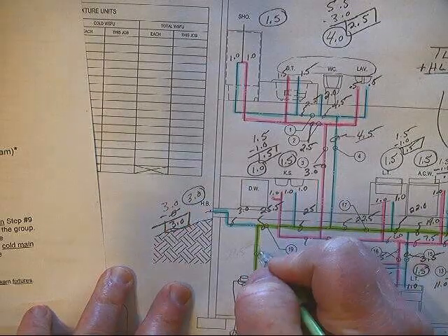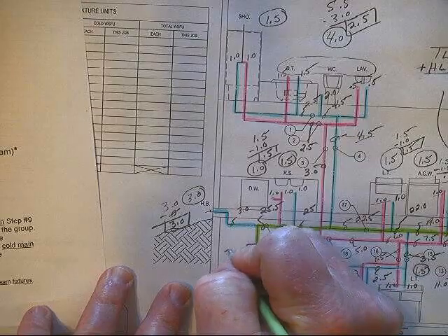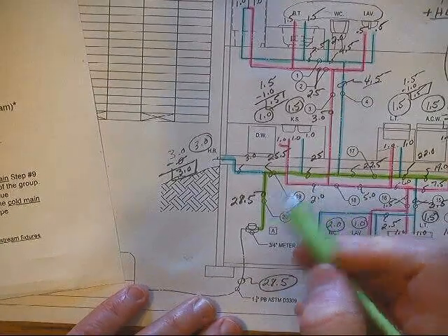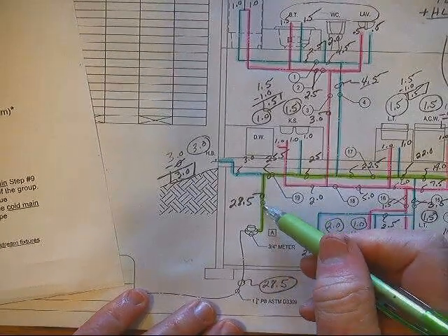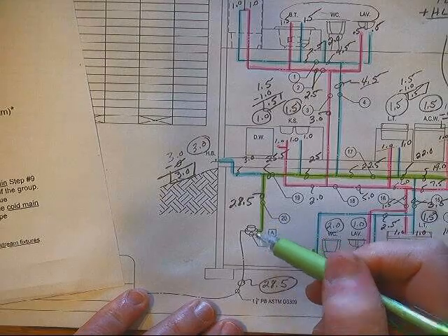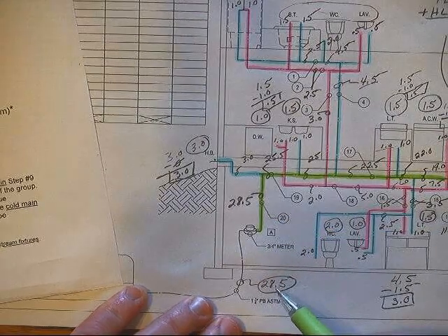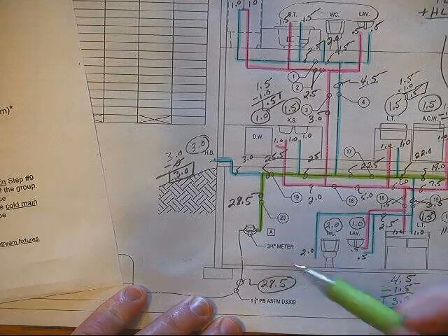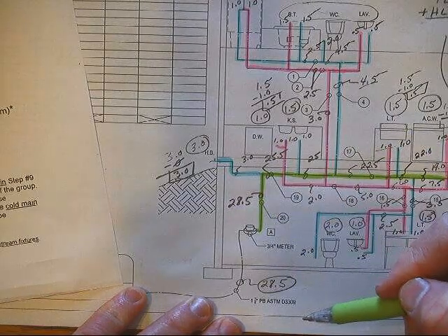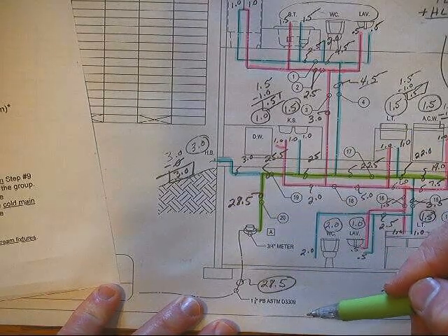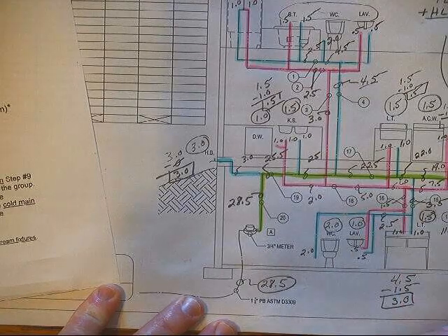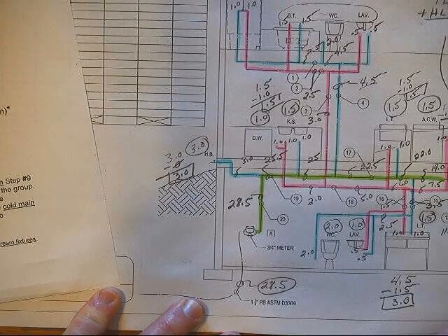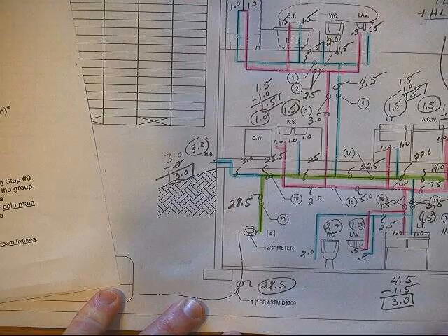We add the 3 onto the cold main, and that takes us to 28.5. And now we can compare the load on the piece of pipe immediately downstream from the water meter to what we started with in the building load, and we'll notice that both of them are identical, and we can rest assured that we have correctly assigned the WSFUs throughout the entire water distribution system. We have now completed this step, and all of the WSFU have been correctly assigned to this drawing.